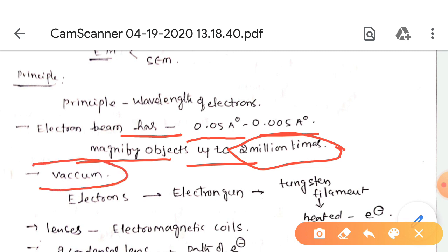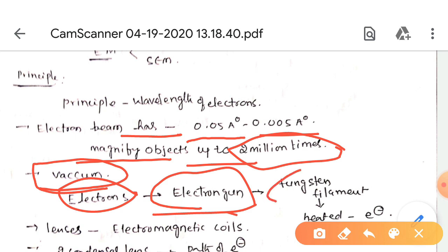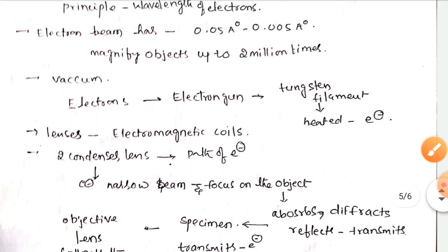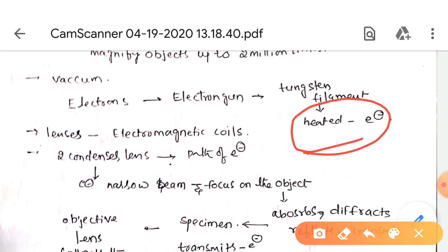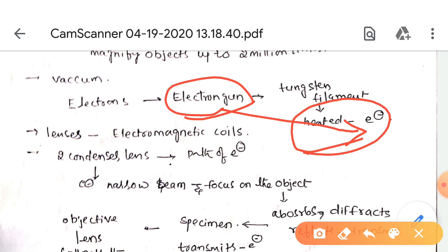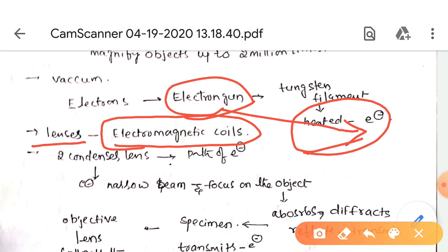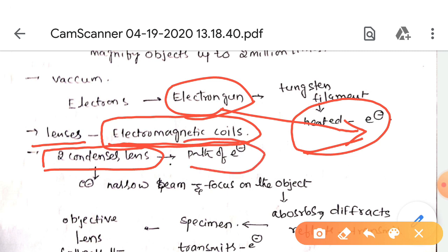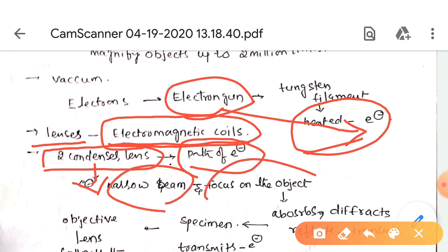The electron microscope works in a vacuum, and electrons are produced by an electron gun. This electron gun contains a tungsten filament; when heated, the electron gun releases electrons. The lenses used in electron microscopes are called electromagnetic coils. Two condenser lenses are present in the path of electrons, and their function is to turn the electrons into a narrow beam focused on the object.